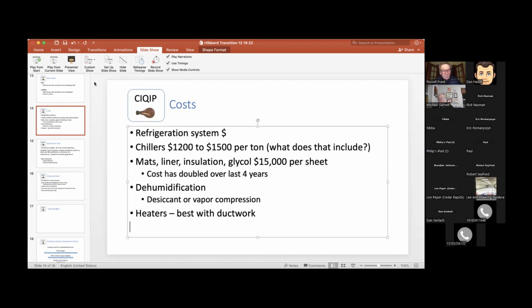The LA Curling Club went out and found a used chiller. I actually helped them find it, and they bought it, and they got a steal on it, but it's an air-cooled chiller, and it does the job for them, but it's much larger than they need. They have 6 sheets, I believe, and they had like a 120-ton chiller. But I would go no less than 10 tons per sheet in Arizona or California, or in fact, I would spec it based on the condensing temperatures. And typically down there would be 115 degrees in those areas.